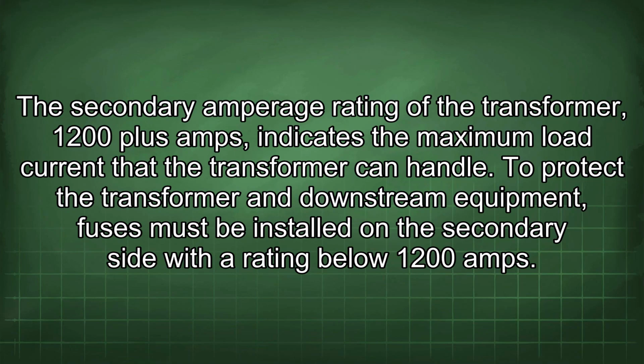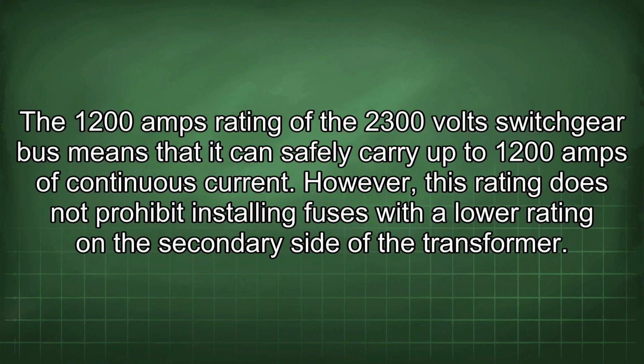The secondary amperage rating of the transformer, 1200 plus amps, indicates the maximum load current that the transformer can handle. To protect the transformer and downstream equipment, fuses must be installed on the secondary side with a rating below 1200 amps. The 1200 amps rating of the 2300 volt switchgear bus means that it can safely carry up to 1200 amps of continuous current.